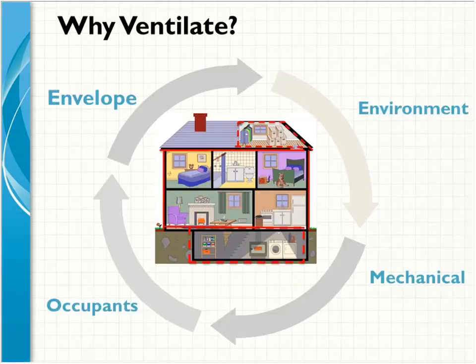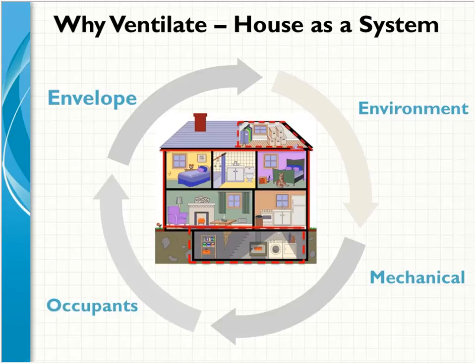Well, over the past 20, 30 years, home builders have gotten much better at making our homes tighter and tighter. And that's good, because people will not accept an uncomfortable, drafty home anymore. But in doing that, they've made it similar to that jar with the lightning bugs in it, and the air trapped inside creates an environment for the occupants that isn't as healthy. So with those tighter homes, that envelope is tighter. We can't rely on the natural leakage of the building anymore to supply fresh air and a healthy indoor air environment for the occupants. So now we have to ventilate mechanically.